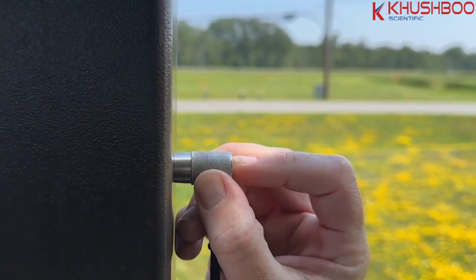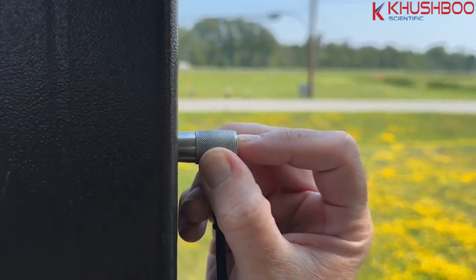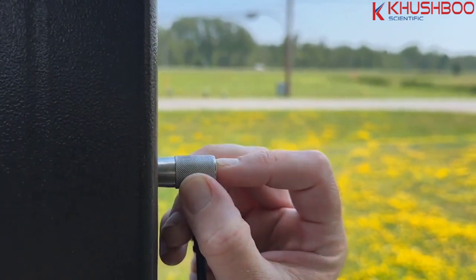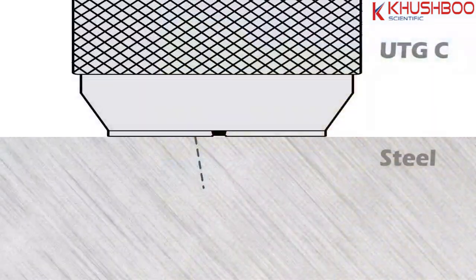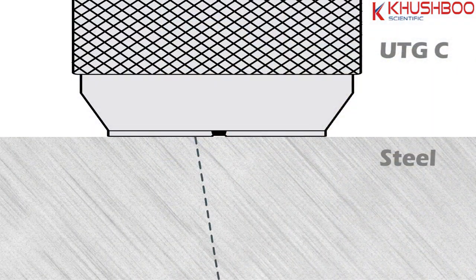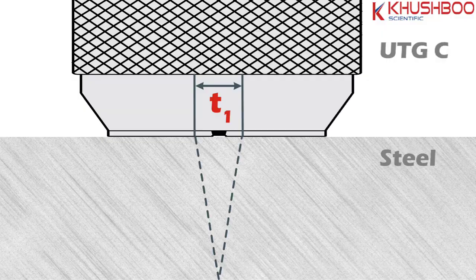When taking a measurement, an ultrasonic pulse is sent into the material, traveling through to the backside. When it encounters an interface such as air or another material, the pulse is reflected back to the probe. The time required for the pulse to propagate through the material indicates its thickness.